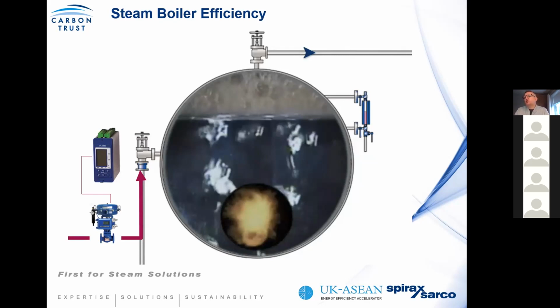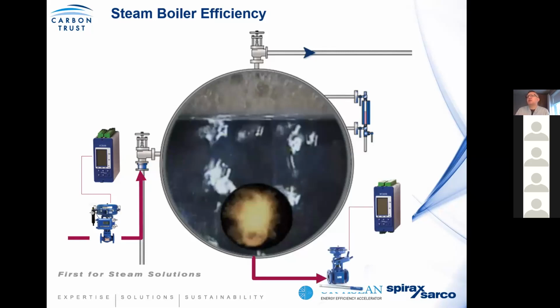Now, you're not seeing your pressure drop from 10 bar to 4 bar, but you could see that your pressure might drop from 10 bar to 9.5 bar each time the pump operates or the valve opens. And again, this has the impact of creating what we call the swell condition and effectively this foaming that's generated on the top of the surface of the boiler water. You should also be looking at your blowdown control, your TDS control, because the quality of the water will determine how reactive the water is to subtle changes. So when you have ineffective control, you create high wet steam. And again, wet steam is an insulator. So it's important you have that kind of control in place.